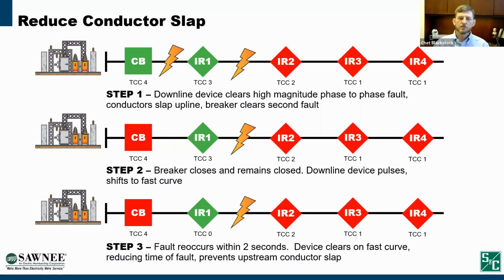And then if we have situations that lend itself to conductor slap, and I will mention that these situations lend themselves more to voltage sags as well because they involve high magnitude fault current. So in this example, we have a fault beyond interrupter 1. This is a phase-to-phase fault. It causes a span to slap, conductors to slap up line. So interrupter 1 clears the initial fault and the circuit breaker clears the secondary fault. Substation breaker closes. Hopefully by that time, the phases aren't swinging so much that they slap again.